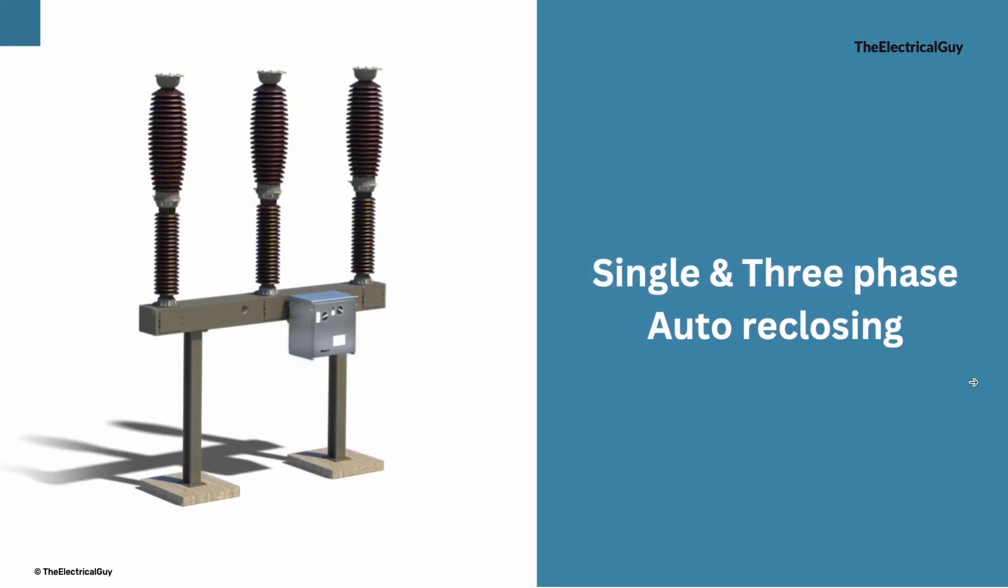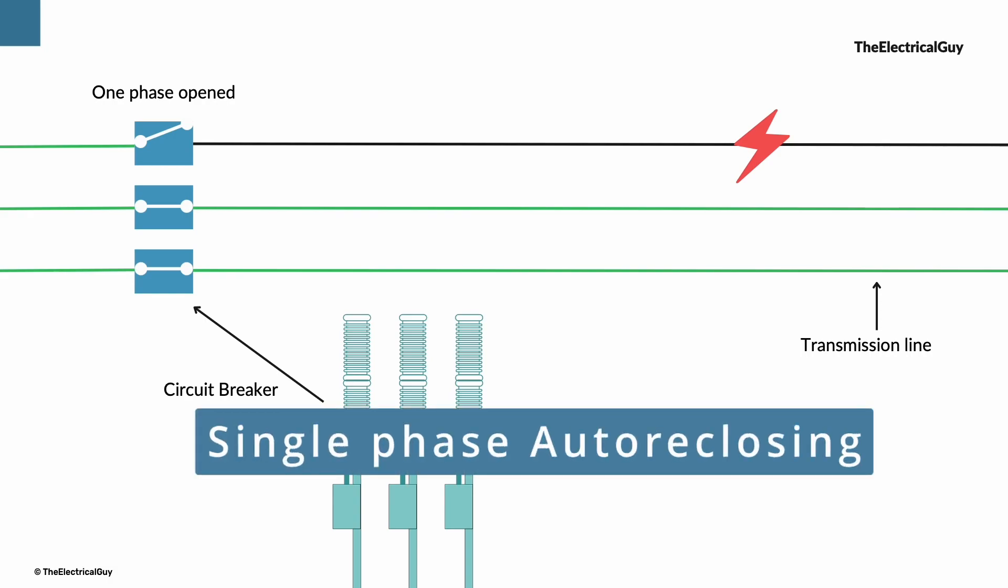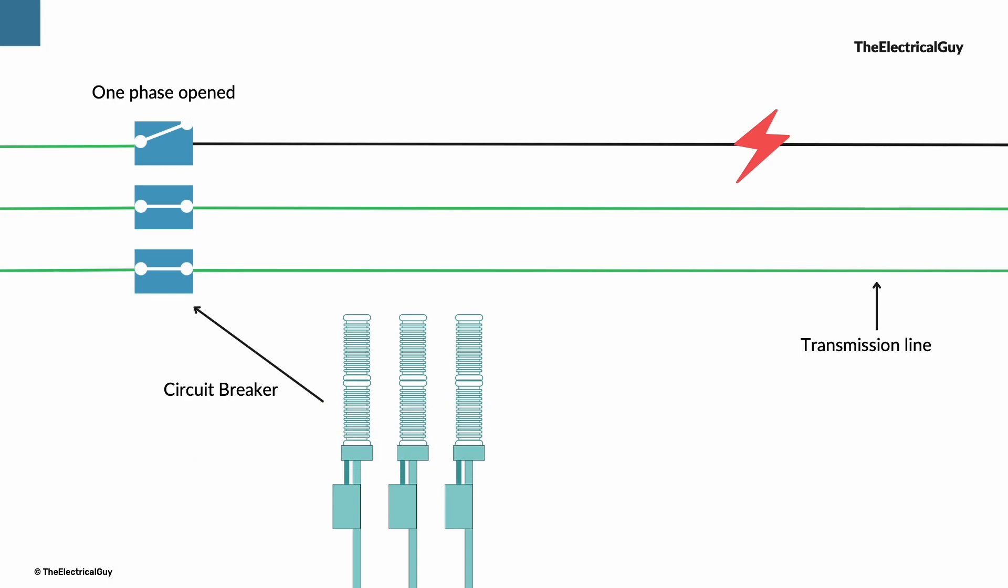Let's say there is a fault only on one phase. Now in such case, only a single phase is tripped and the balanced two phases are still in operation. And circuit breaker will try to reclose that one faulty phase only. And this type of reclosing is called as single phase auto reclosing because we are only trying to reclose one phase.